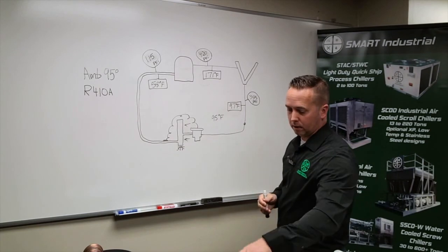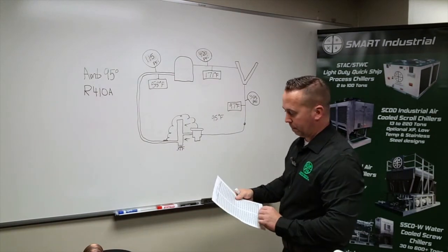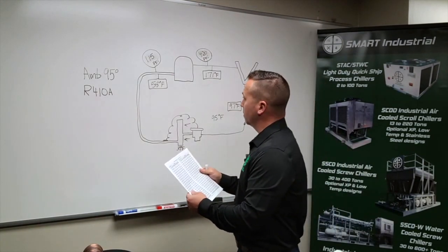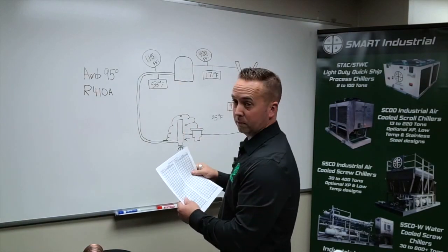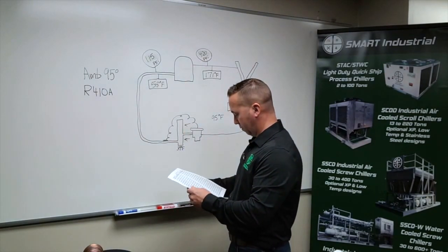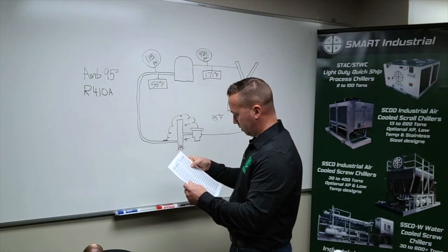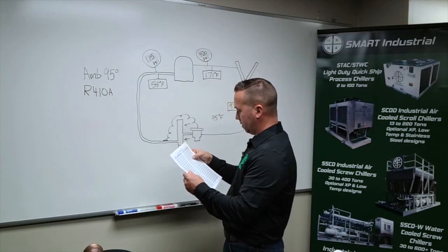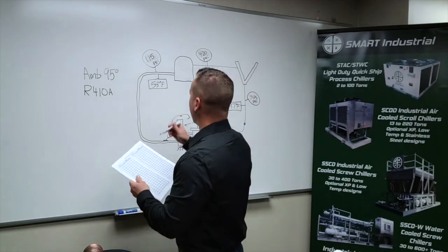Now, I go to my PT chart and I look at 115 psi. At 115 psi, 410A refrigerant is 39 degrees.